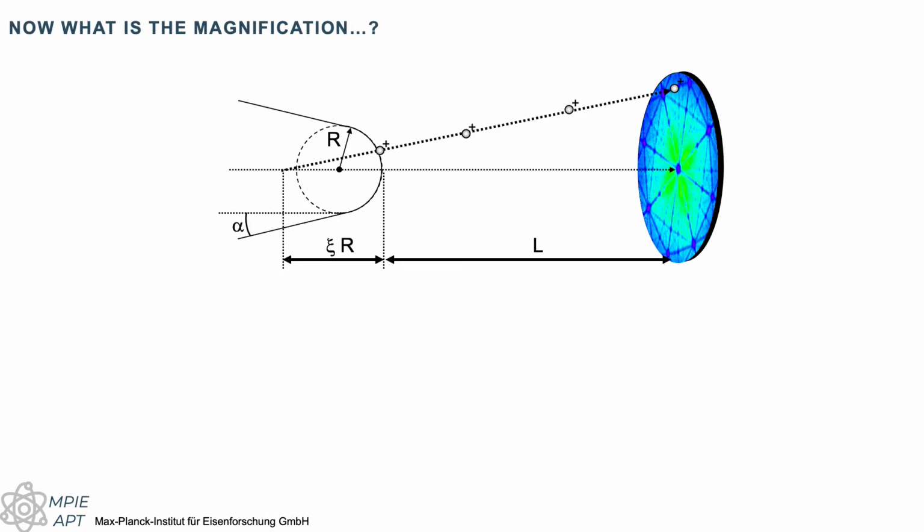So if we take all of this into account, we can build a fairly simple model for the reconstruction. That was done in the early 90s. We can assume that the ions will fly along a straight line, that all of the trajectories will cross at a given point that is unique along the specimen axis, away from the center of the spherical cap, at a distance which is this image compression factor times the radius.